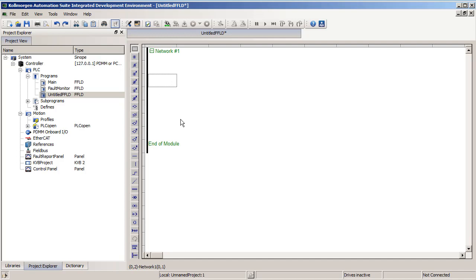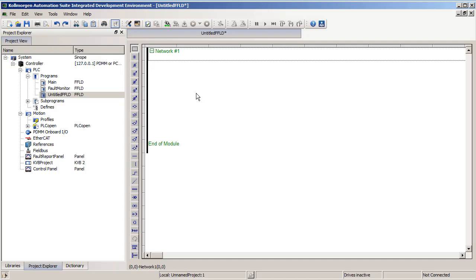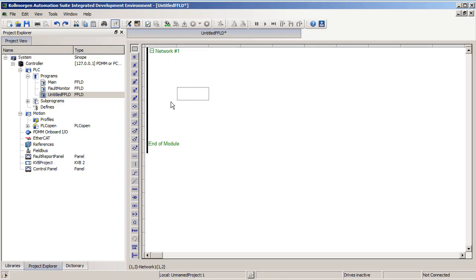It is beneficial to add multiple networks because once you have them, you can close them. It helps troubleshooting, especially when you break your code into smaller sections. Also later when you get into jumping, you can only jump to the top of a network. So if you're going to use jumping in your program, you're going to have to break it down to multiple networks.